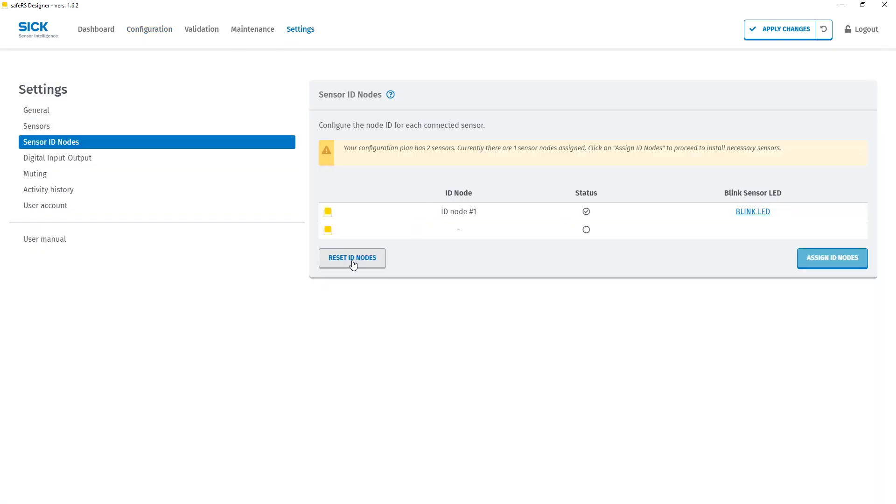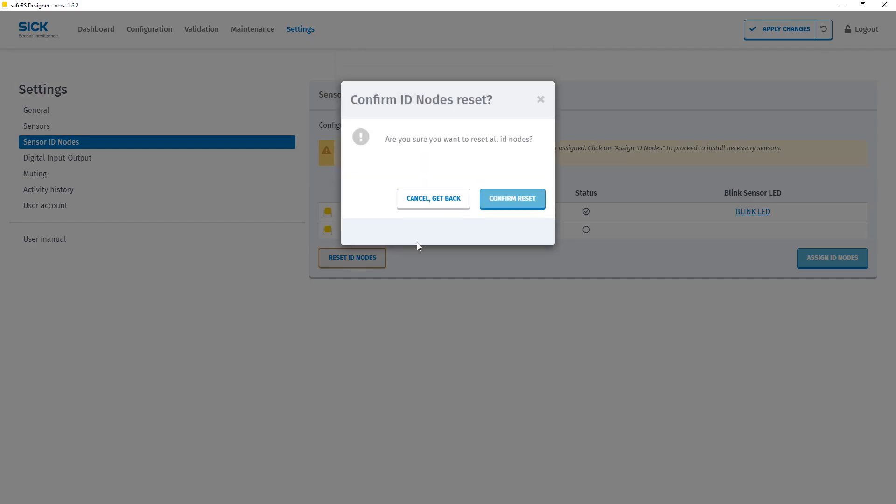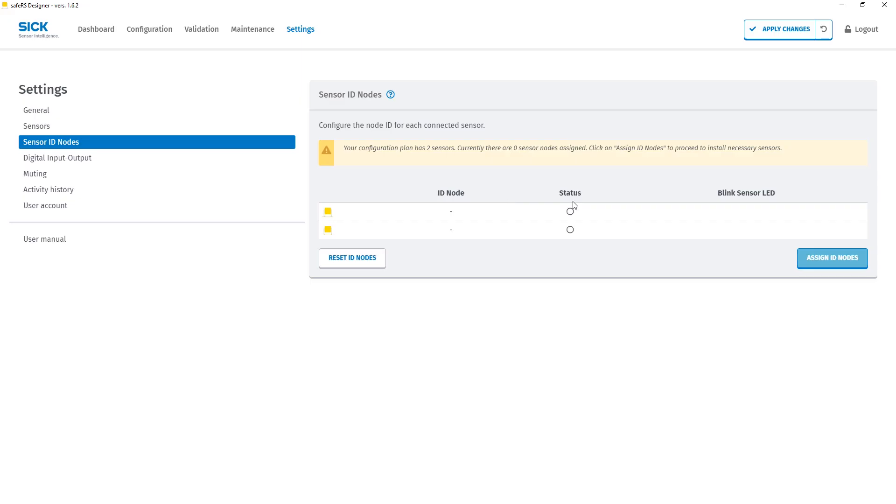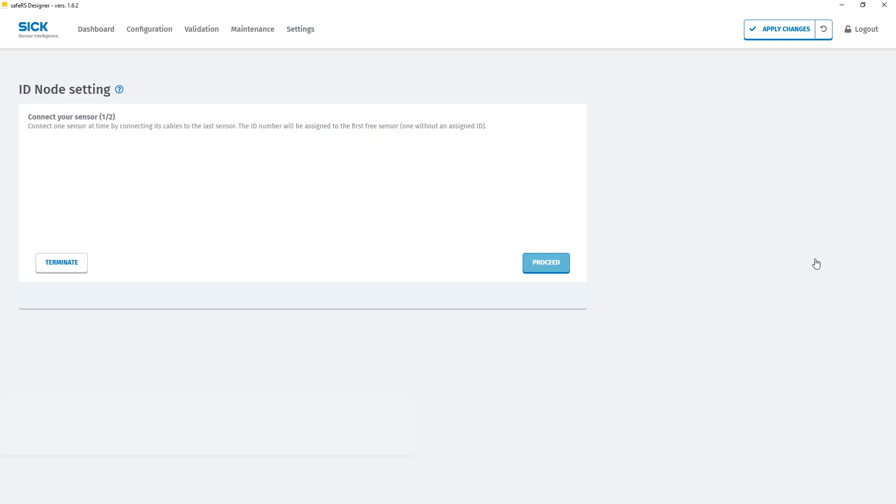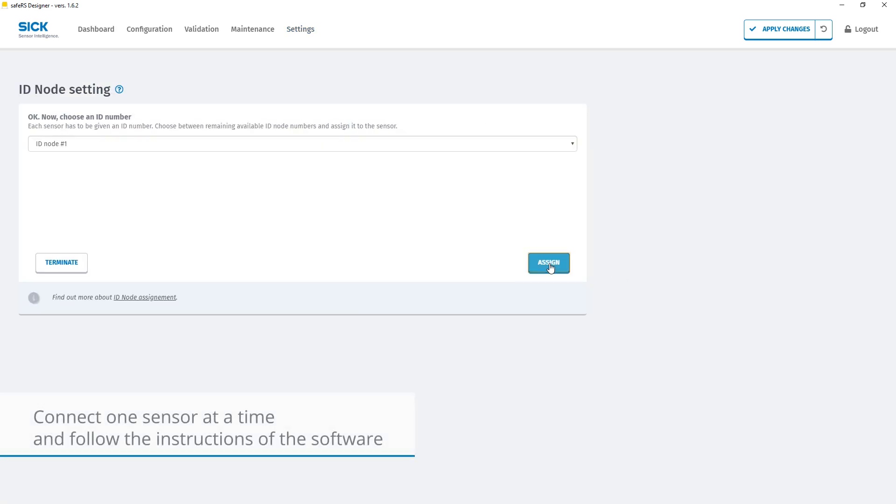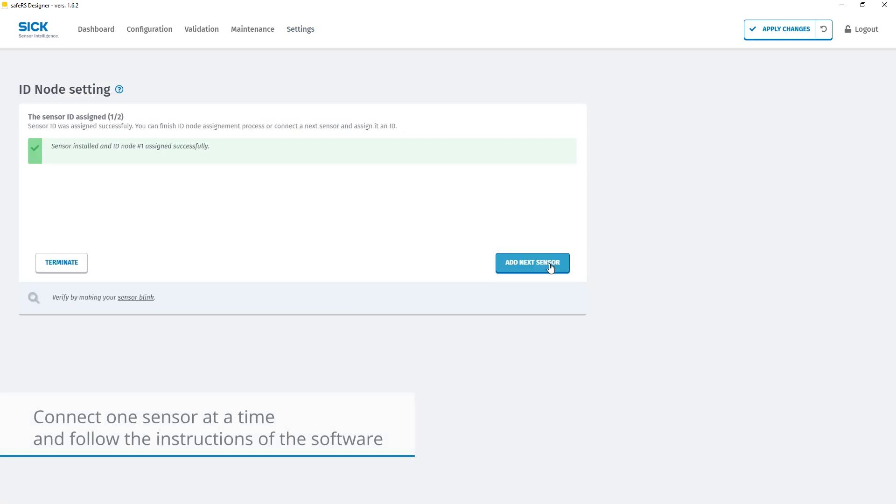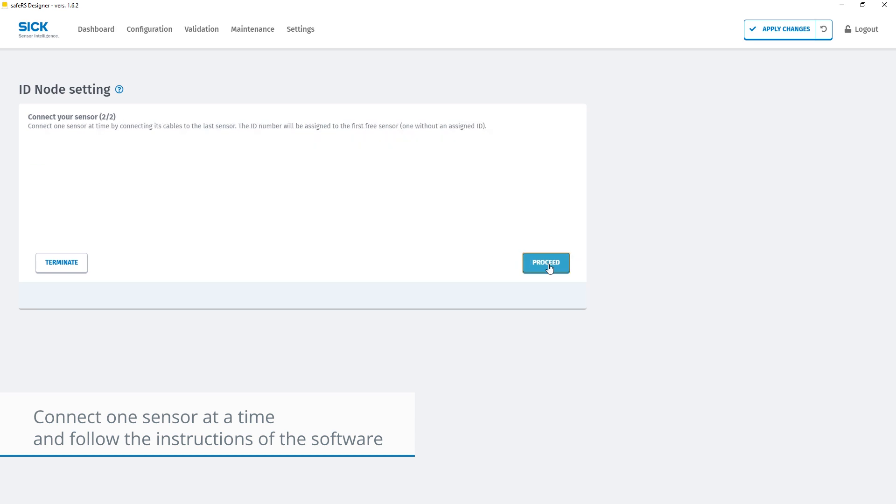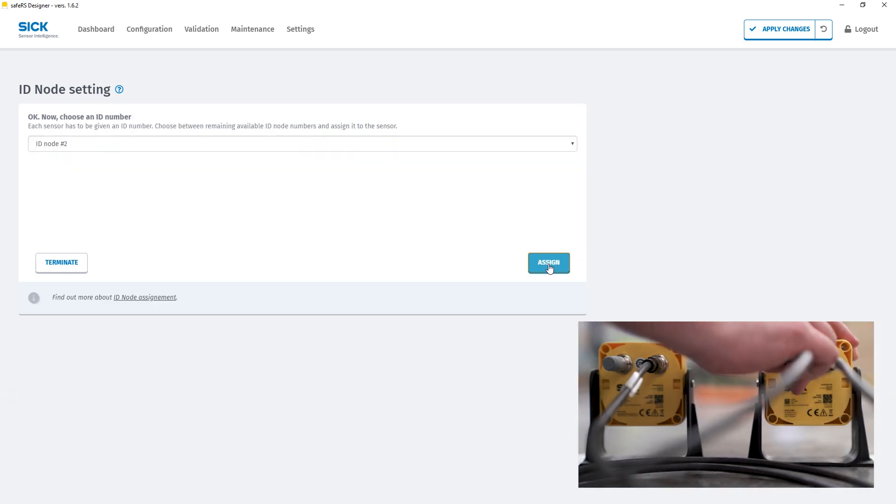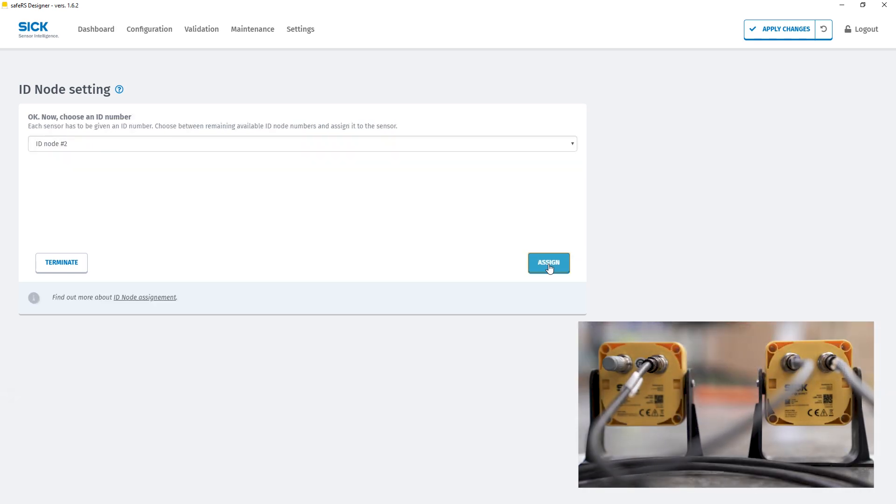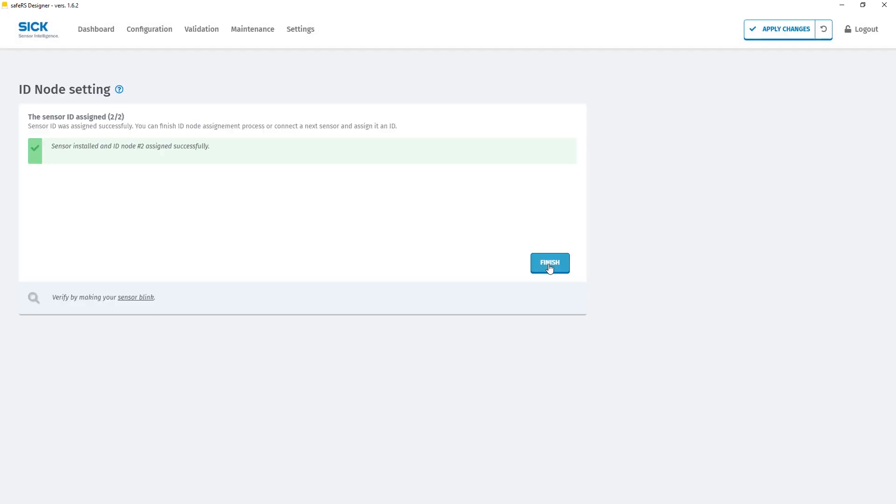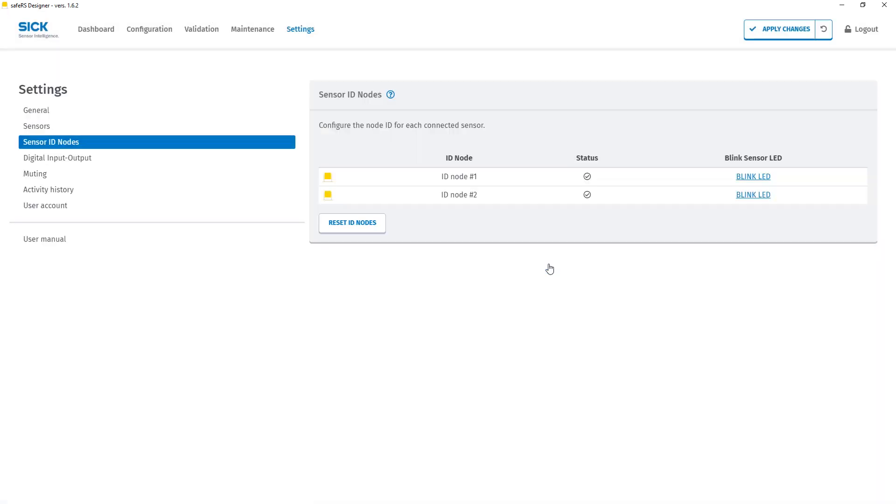First we need to reset the ID nodes in the software. Then we have to physically connect the first sensor of the chain to the controller and assign the first ID. After that we physically connect the second sensor to the first as a daisy chain and assign the second ID. Now the controller knows that there are two sensors connected to it.